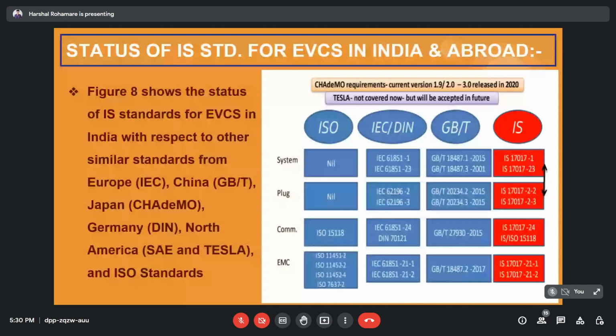Secondly, the communication requirement of electric vehicle charging stations for all countries except Germany and Japan are common, as per the ISO 15118 series of standards, which are adopted directly by IEC, GBT, and IS standards for countries like the United States, Europe, China, and India, with different standard numbers. Germany and Japan use DIN 70121 and CHAdeMO standards respectively for their communication requirements. The standards IEC 61851, GBT 27930, and IS 17017 are equivalent, and the ISO 15118 series of standards provide the general requirements common to all countries.